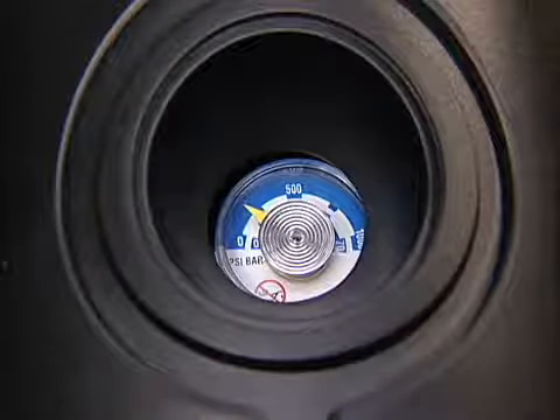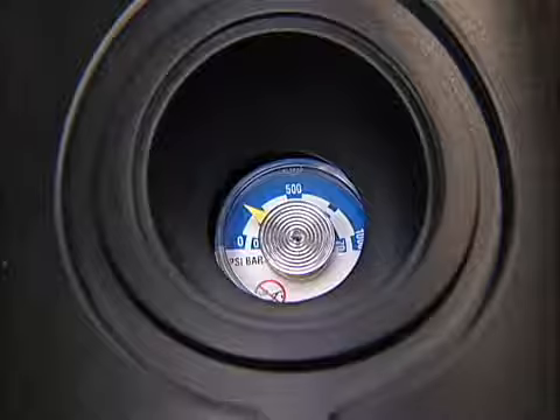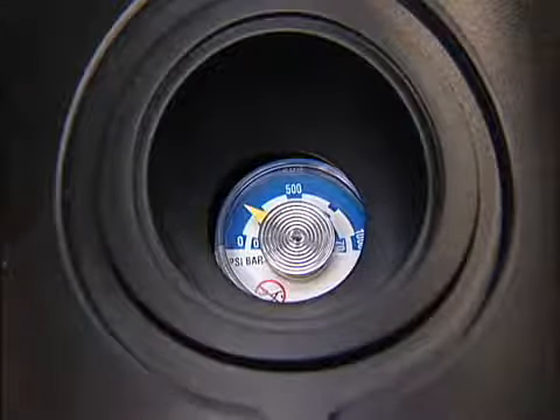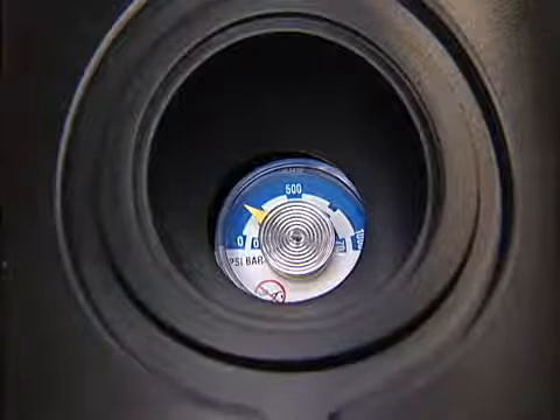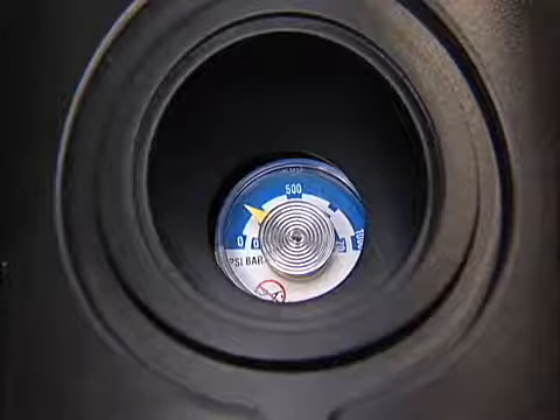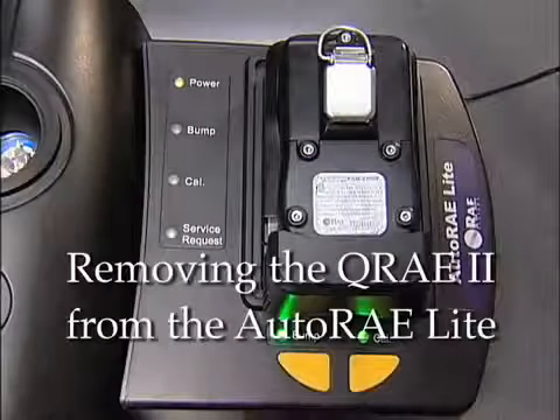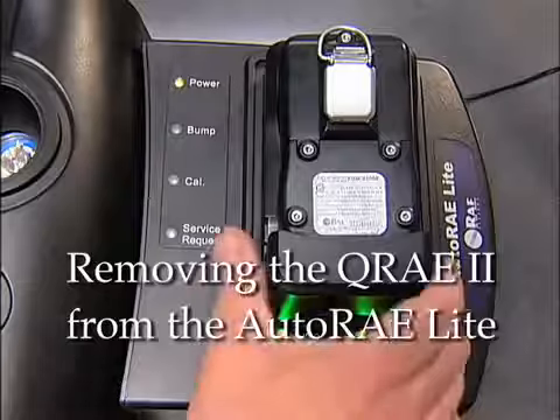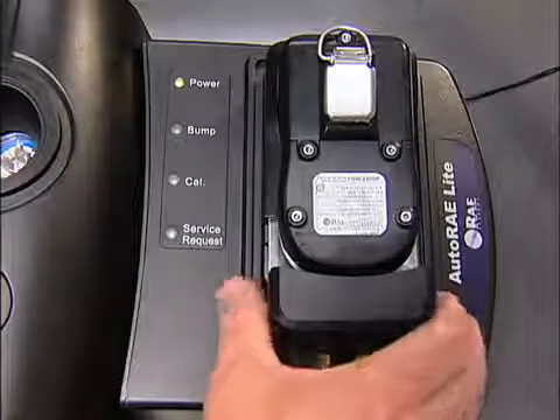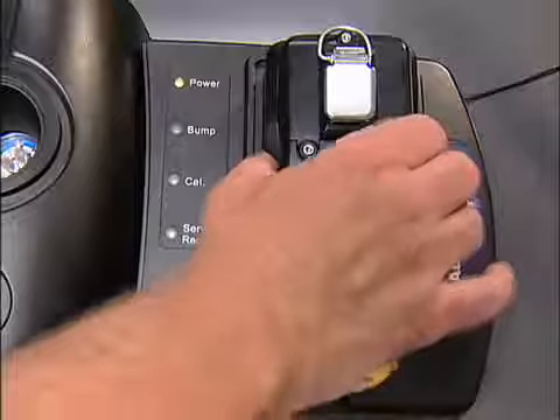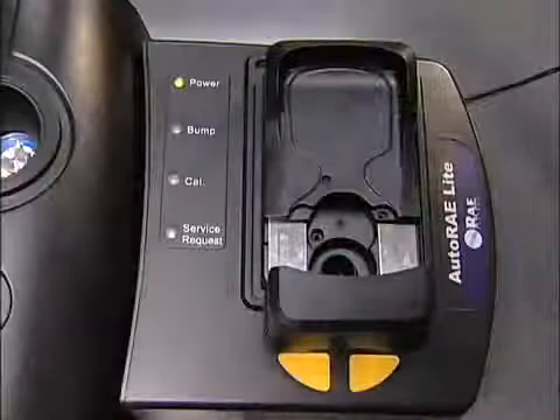If a bump test or calibration fails, check the calibration gas pressure and try again. If it fails again, it is possible the sensor is depleted and must be replaced. When the bump test or calibration is complete, remove the QRAE II from the dock by pulling back on the locking mechanism to release the QRAE II straight out.